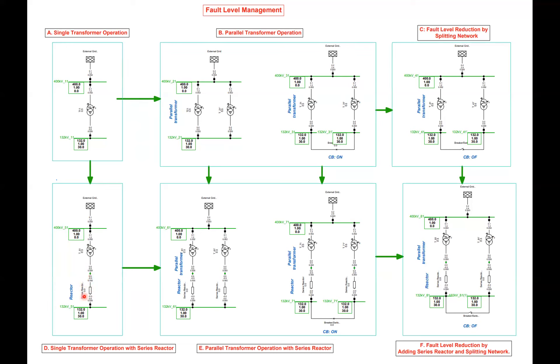So these are the techniques. Everything is the same — just add the reactors in series, switchable on and off. Looking at these two cases: fault level reduction by adding a series reactor, and by splitting the network.